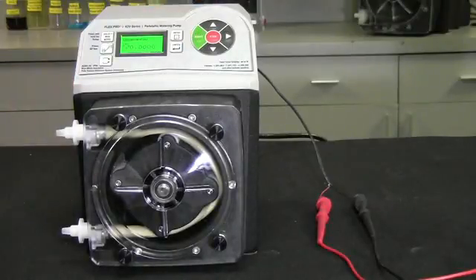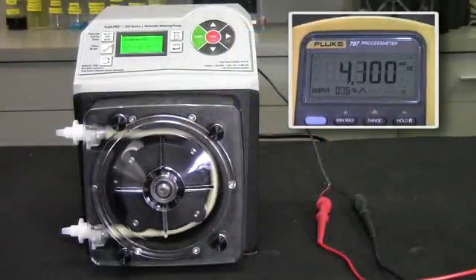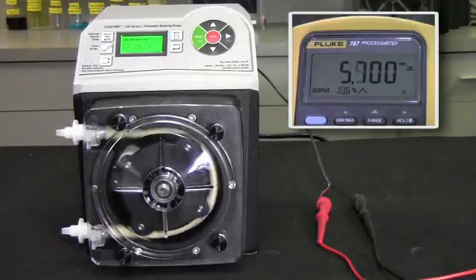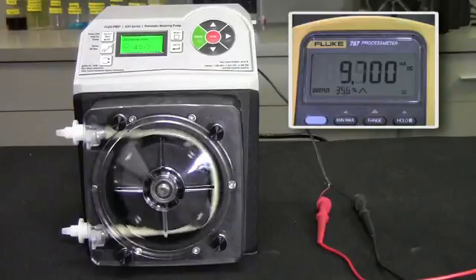Press the start button on the pump and activate the Fluke meter. Notice how the pump operates in relation to the output signal from the 4 to 20 milliamp generator. The pump is operating correctly.